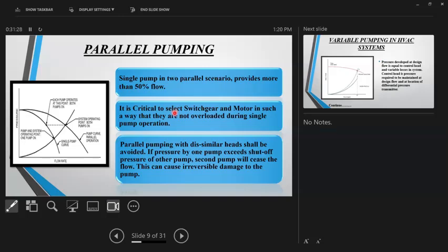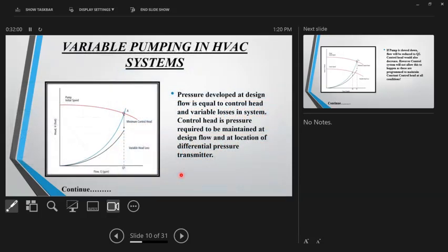Next, parallel pumping with dissimilar heads shall be avoided. I think this is quite logical: if you have pumps with, let's say, 6 bar and 3 bar, and you try to run them in parallel, you have a problem, right? If the pressure of one pump exceeds the shut-off head of the other pump, the second pump will cease the flow. It won't operate, and it can cause irreversible damage to the pump. There is always an imbalance in flow and head, and that's the reality. Now let us see how to circumvent this to the best of our ability.